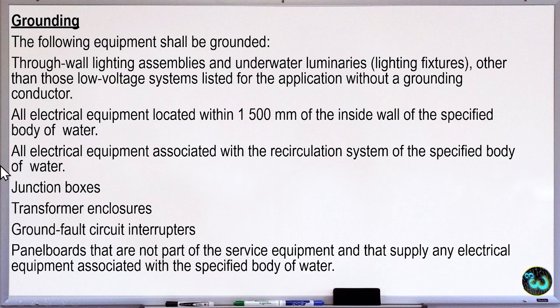All junction boxes, all transformer enclosures, including the enclosures of our ground fault circuit interrupters. Then panel boards that are not part of the service equipment and that supply any electrical equipment associated with the specified body of water. So all panel boards, even those that do not supply the service equipment or the pump, but supply any electrical equipment associated with the pool, like the lights. So the panel board must also be grounded.